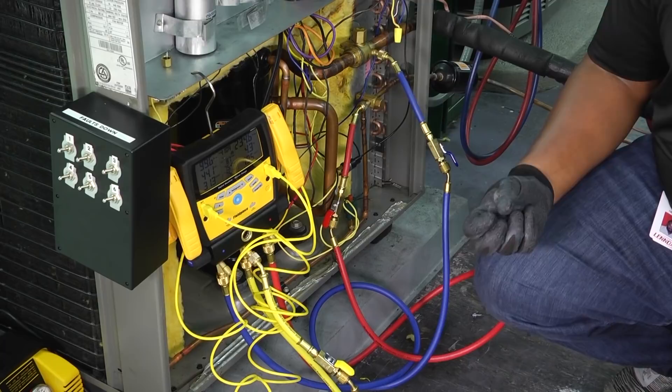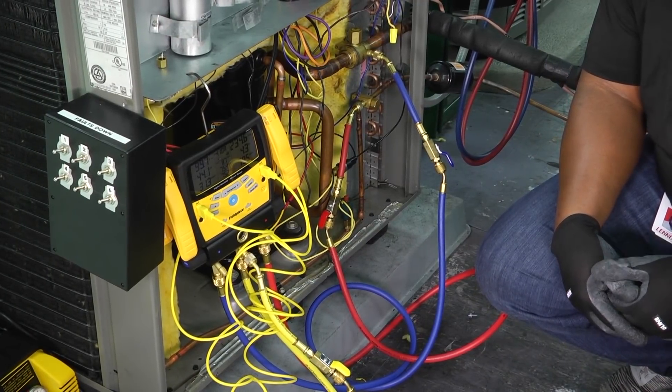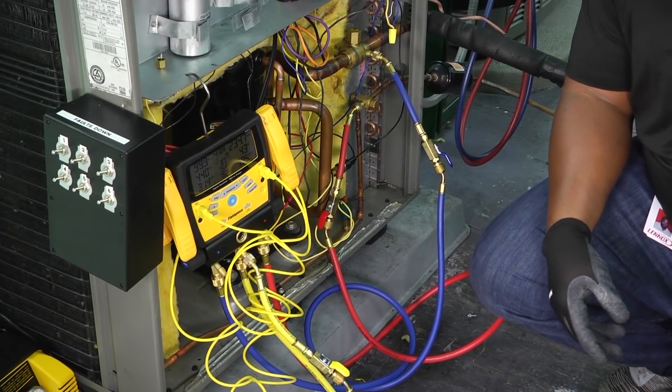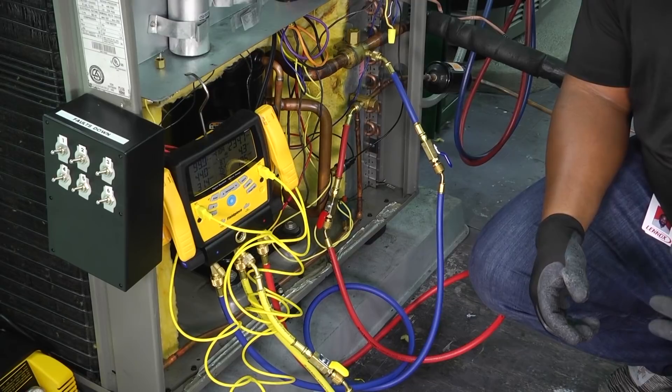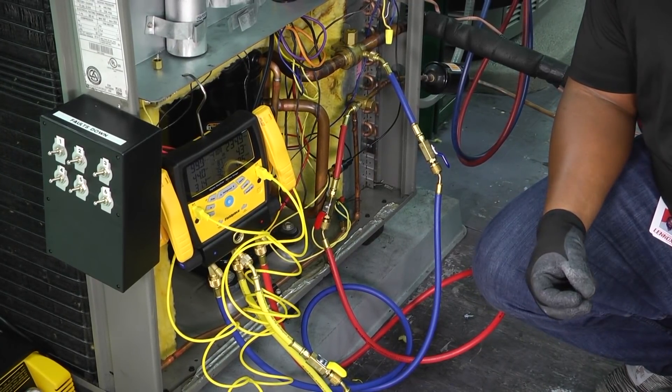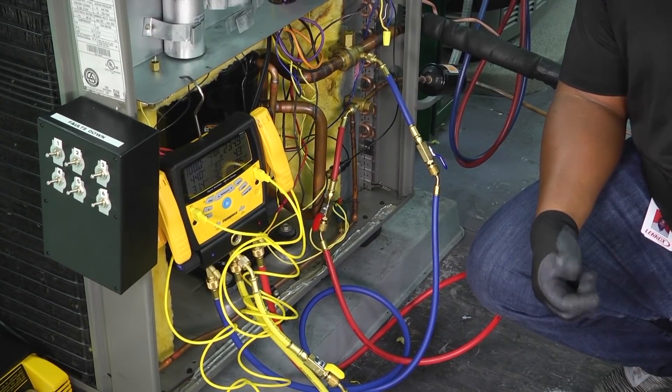Well, how do we know? Good question. Well, because we already figured out that we had some charts to kind of tell us what to do based on superheat. But for subcooling, it's a little different. Now, some manufacturers will have a chart on the data plate that gives us the information for the desired subcooling for that particular system.